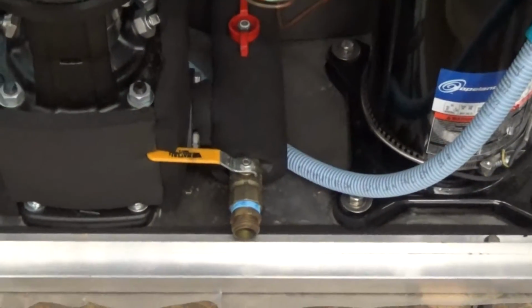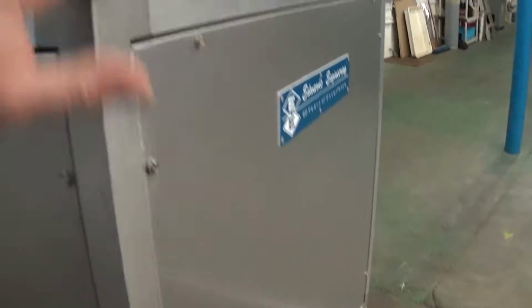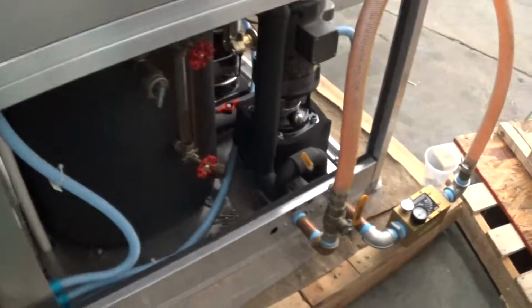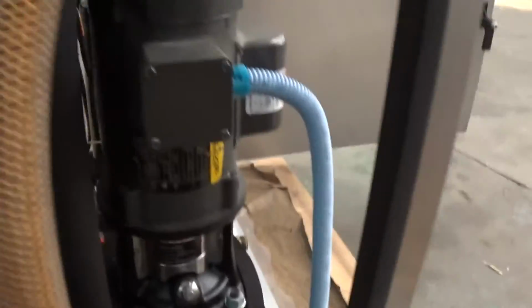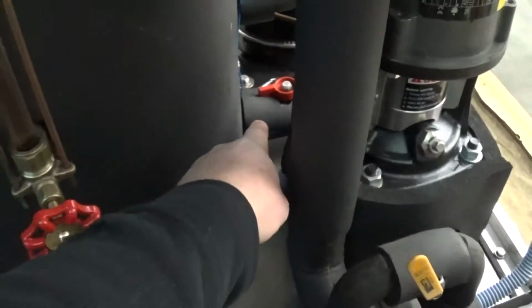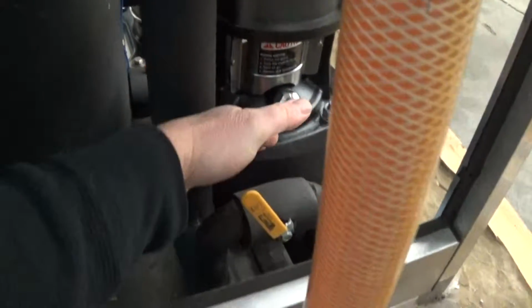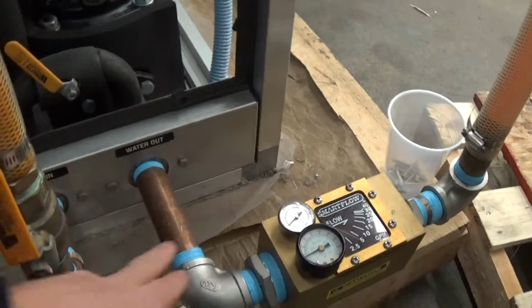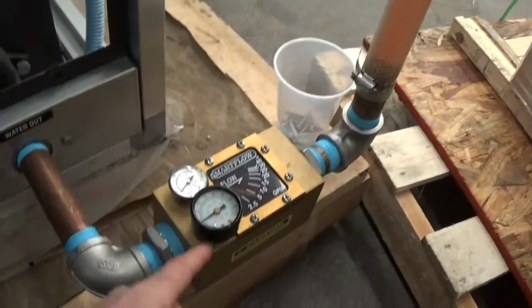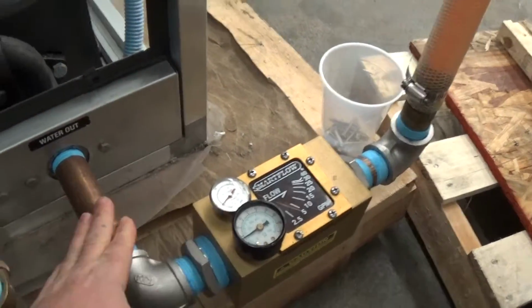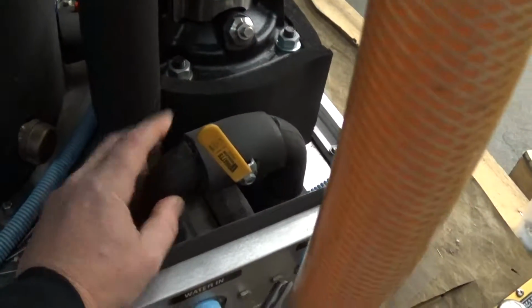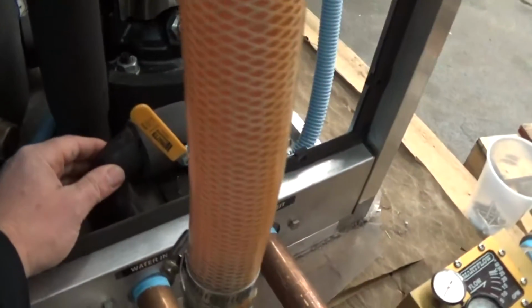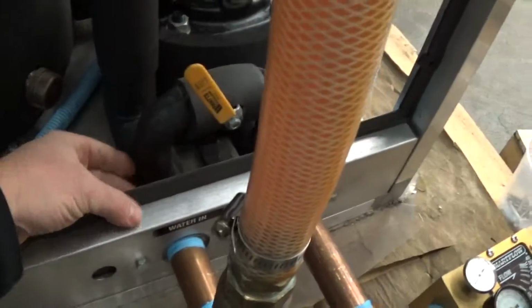So you have your drain. And we do have all the side covers. For this test, we can have the side covers off. However, the top side covers on a unit like this should remain on. So here we have our pump. Our pump draws from the tank here into the pump, okay? Then it comes here out to your process. In this case here, we just created a loop, and we're going through our flow meter and pressure gauge. There's an internal bypass here, and leave that kind of cracked half open upon initial startup. And then this is your return. It comes back and discharges back into the glycol reservoir.